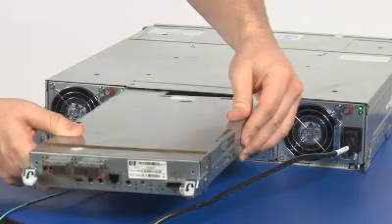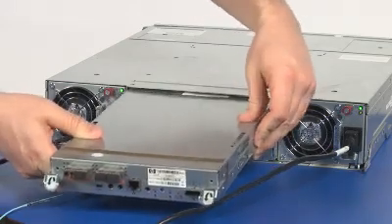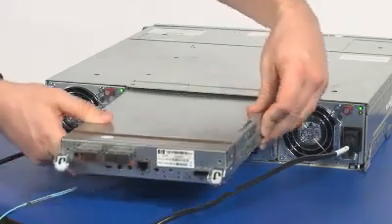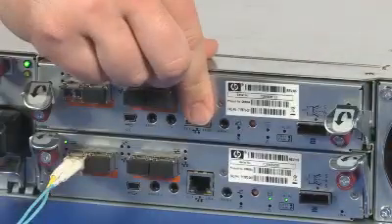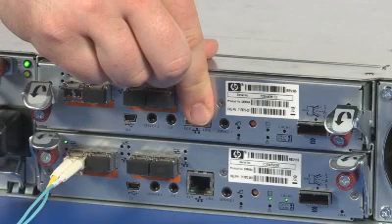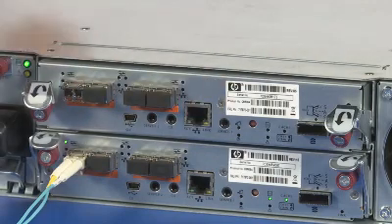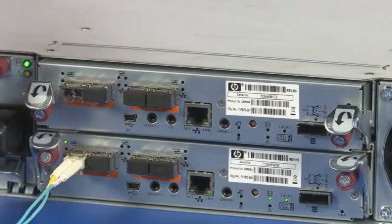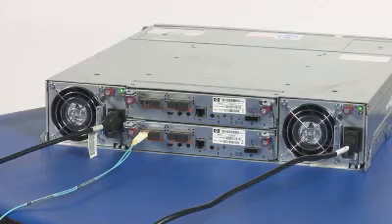Replacement. With the latches in the open position, slide the module into the enclosure as far as it will go. Press firmly on the top center of the module to facilitate insertion, ensuring that the module is well seated and flush with the chassis.